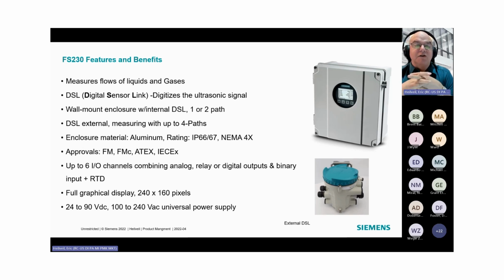So when you ask what degrees of uncertainty in pipe diameter and wall thickness are considered for a 1% of rate flow accuracy, I would say that standard pipe, Schedule 40 or whatever you happen to have, will most likely deliver a flow accuracy of 1% of rate or better. So standard pipe in decent condition. That means the internal condition is reasonable. You can have scaling, you can have some buildup, but the challenge is that the more buildup there is, the smaller the internal volume. It's very difficult for me to give you a measurement of uncertainty of pipe diameter and wall thickness for 1%, but 1% is usually the worst we do. If you want to get better than 1%, that's when you really start getting into the engineered pipe.